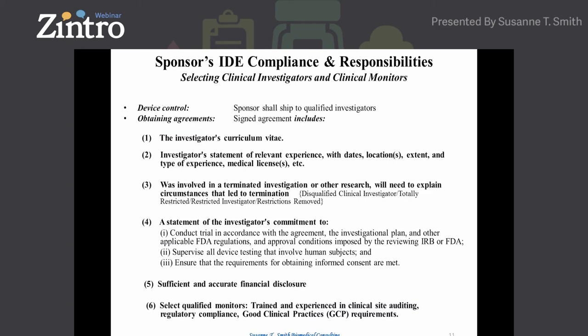Investigators must supervise the device. Usually devices are locked up in a secure area so nobody else can use them on a patient who is not in the study. Device accountability — the numbers shipped, lot numbers, date of implantation, and which patient — must be tracked for traceability and kept in compliance at all times. The investigator maintains regulatory binders with all documents, now often electronic. The sponsor must also disqualify investigators when necessary: an investigator who repeatedly or deliberately fails to follow the investigational plan, deviates from the protocol, or submits false information will need to be disqualified.